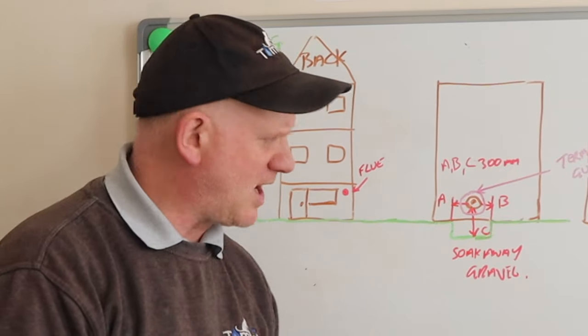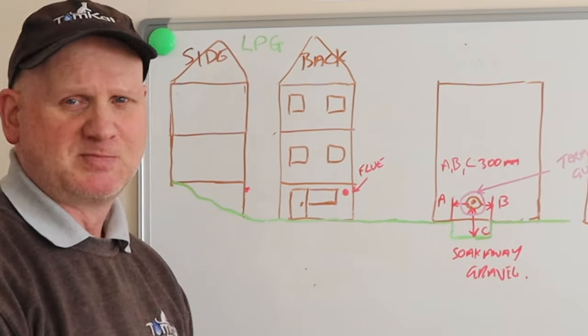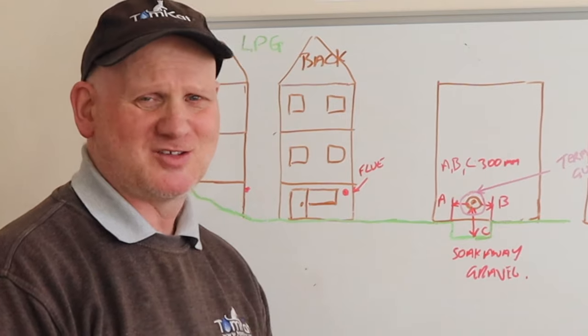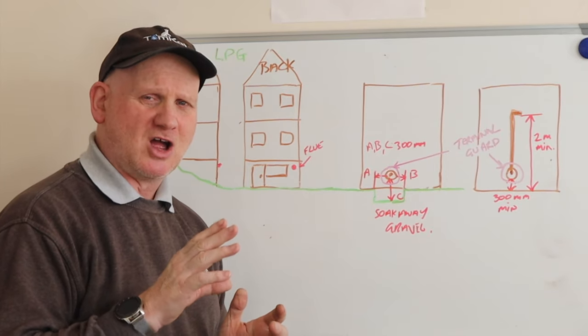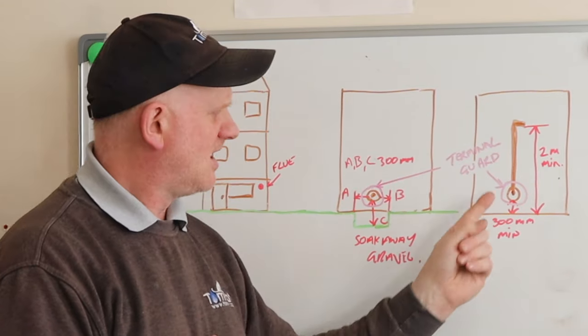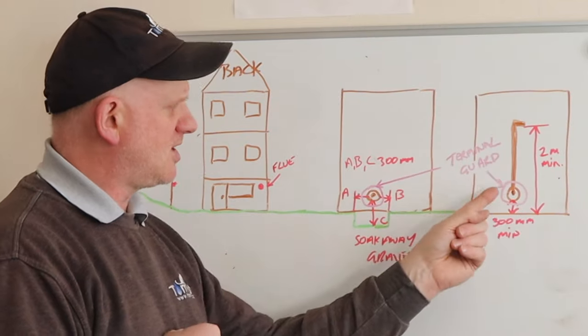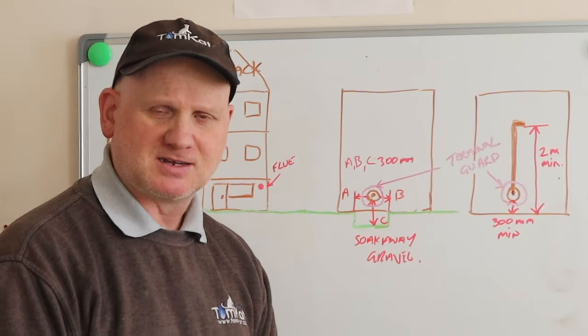The excavated area must act like a soakaway with gravel so water drains away, and the flue must be slightly higher than ground level so that if it floods there is still somewhere for water to go. This is not advisable and you would need permission from the boiler manufacturer. A common approach is to position the flue 300mm above ground and then use a plume management kit to take the termination above two meters, because you don't want the plume to be a nuisance.